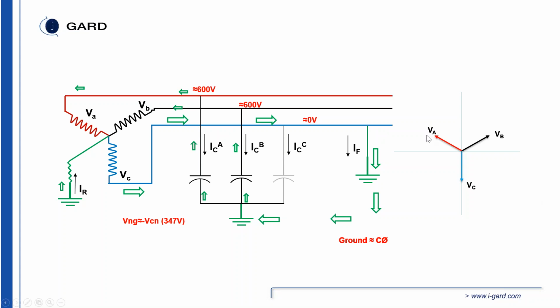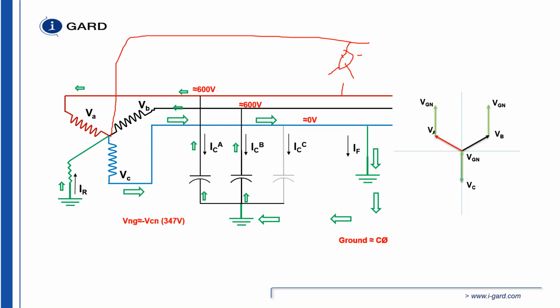So when you have a normal system, A, B, and C phase are 347 volts to ground and 120 degrees apart. When you have a fault on your system, all the voltages shift, but more importantly, the neutral shifts as well.